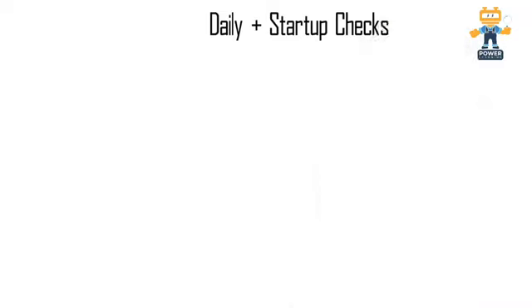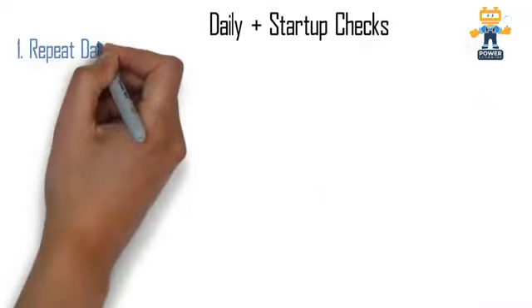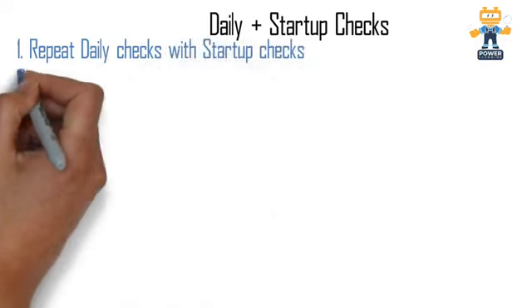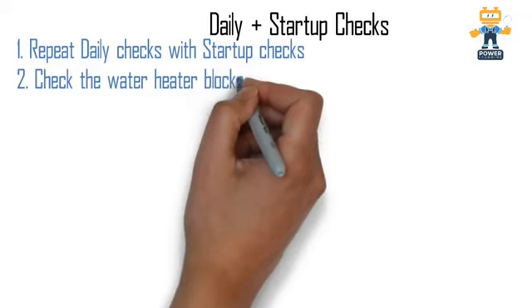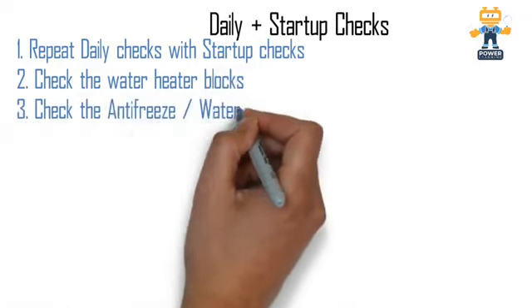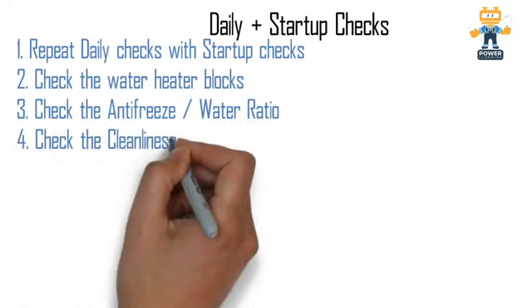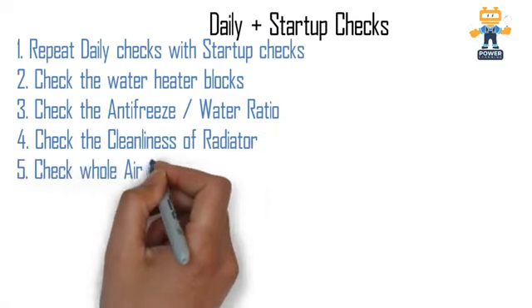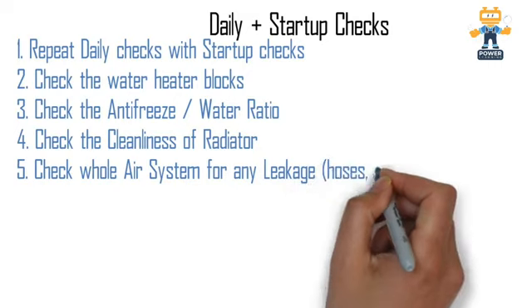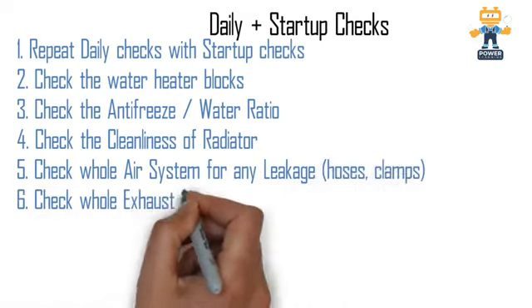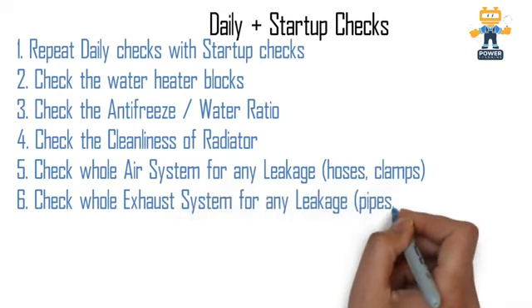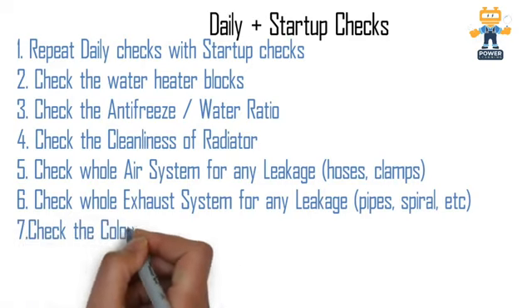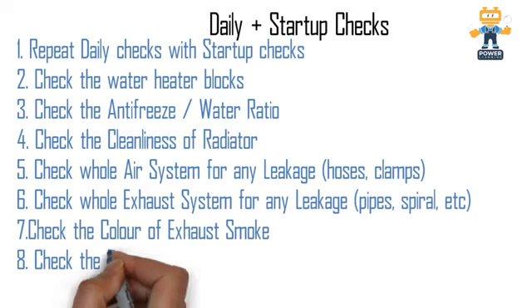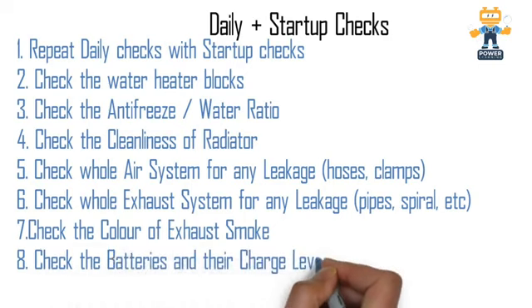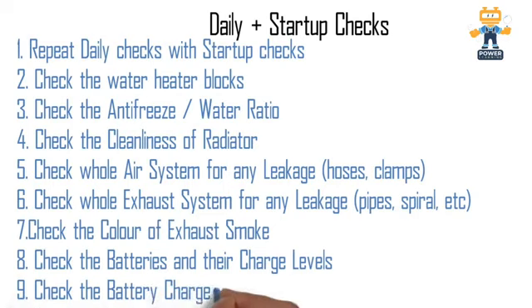Now daily plus startup: we have to do the first list plus add this list with the startup checks, so it covers all the points before starting. Check the water heater blocks, and check the antifreeze and water ratio in the radiator. Number 4 is check the cleanliness of the radiator. Before starting we have to confirm the radiator is clean and okay for operation, and check the whole air system for any leakages, like hoses and clamps. We have to retighten them. Number 6 is check the whole exhaust system for any leakages, pipes, spiral, etc. Number 7 is check the color of the exhaust smoke while the generator is running. Number 8 is check the batteries and their charge levels. Number 9, check the battery charger and charging alternator while the generator is running.